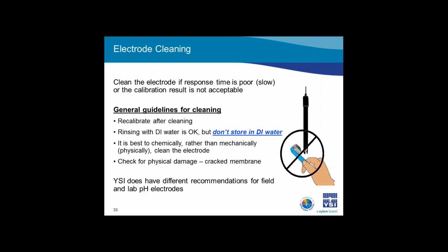If you are having slow electrode response or difficulty calibrating, try cleaning the electrode. We will go through the cleaning steps in a moment, but here are some quick precautions on cleaning. First, you will always want to recalibrate after cleaning. Remember, your data is only as good as your calibration. Next, rinsing in DI water is part of the cleaning process and, in fact, also part of the calibration process we reviewed. Even though we recommend rinsing in DI water, it is very important to note that a pH sensor should never be stored in DI water.